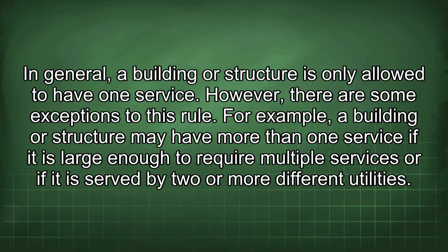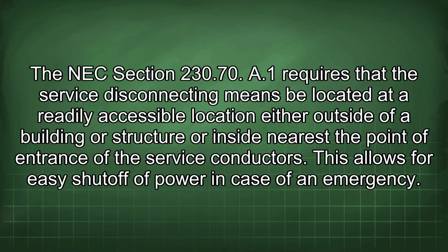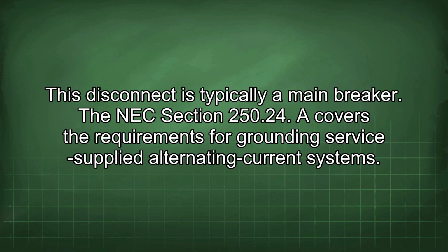For example, a building or structure may have more than one service if it is large enough to require multiple services or if it is served by two or more different utilities. The NEC Section 230.70(A)(1) requires that the service disconnecting means be located at a readily accessible location either outside of a building or structure or inside nearest the point of entrance of the service conductors. This allows for easy shut-off of power in case of an emergency. This disconnect is typically a main breaker.